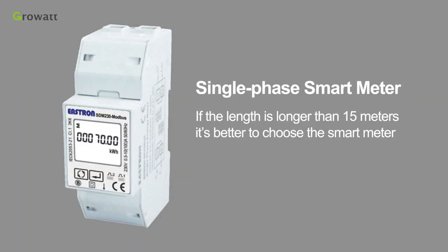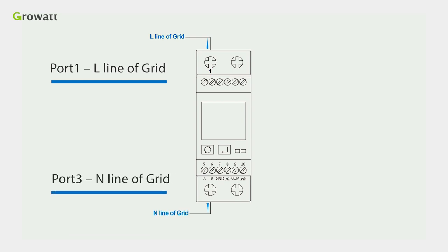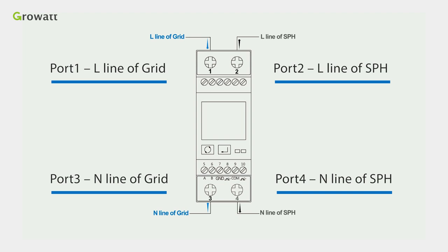If the length is longer than 15 meters, it's better to choose the smart meter. Firstly, connect the port 1 to the L line of grid, port 3 to the N line of grid, port 2 to L line of SPH, and port 4 to N line of SPH.